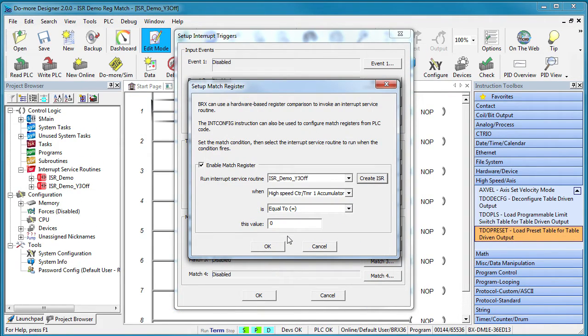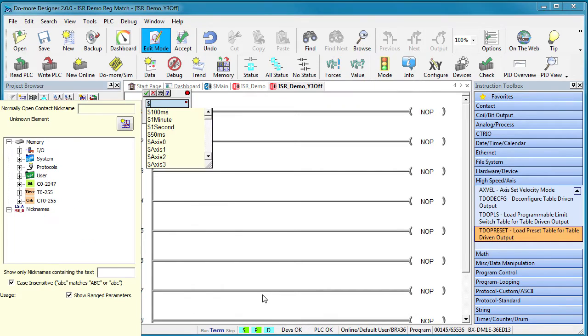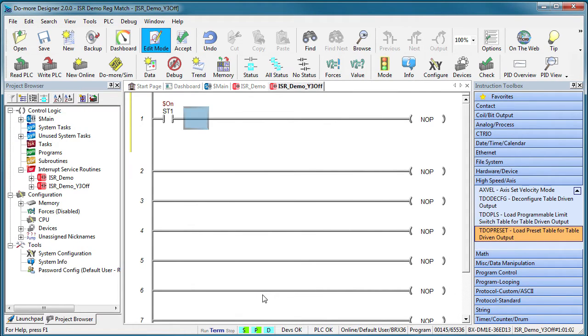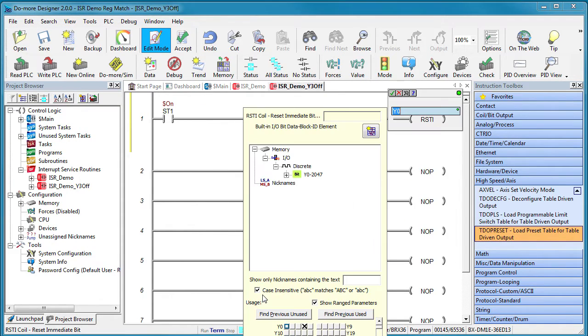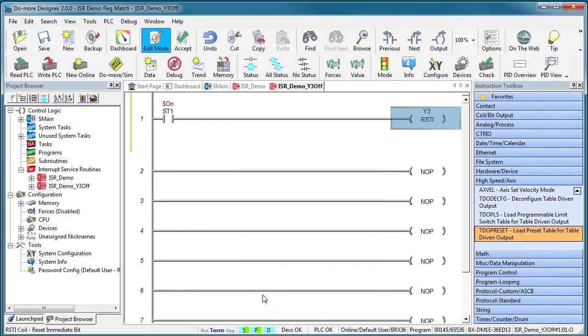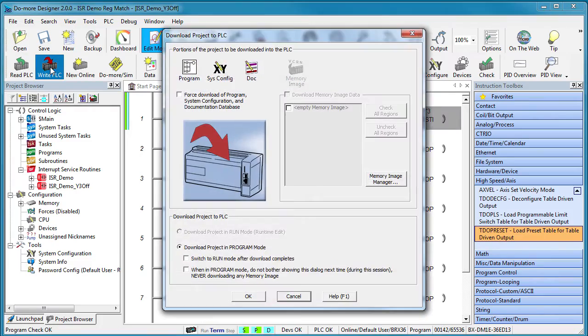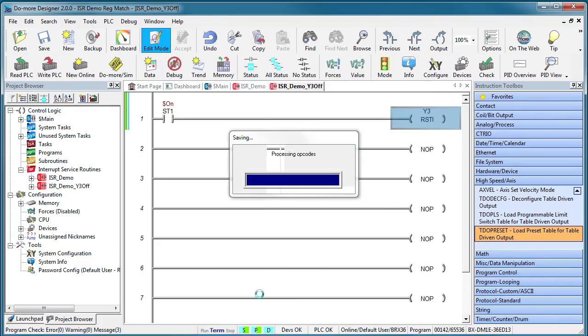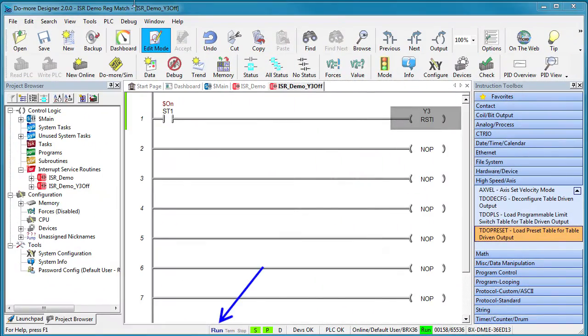And when that same accumulator is equal to 1500, we want to execute that ISR routine. And in that ISR, we'll use an immediate reset instruction to turn Y3 off so it will turn off immediately and not wait for the bottom of scan like all of the other outputs. Accept all that. Write it out. And make sure the PLC is back in run mode.